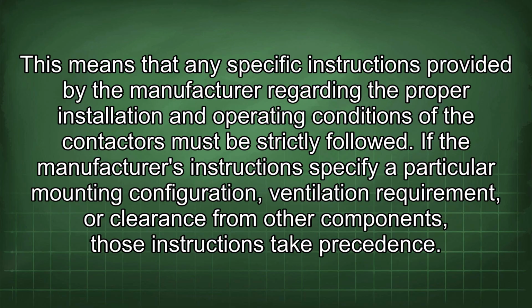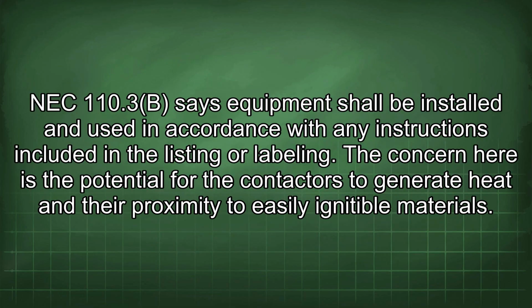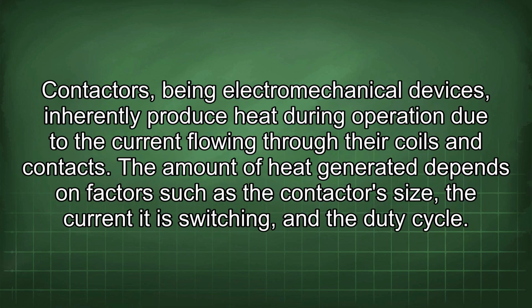If the manufacturer's instructions specify a particular mounting configuration, ventilation requirement, or clearance from other components, those instructions take precedence. NEC 110.3(B) says equipment shall be installed and used in accordance with any instructions included in the listing or labeling. The concern here is the potential for the contactors to generate heat and their proximity to easily ignitable materials. Contactors, being electromechanical devices, inherently produce heat during operation due to the current flowing through their coils and contacts.